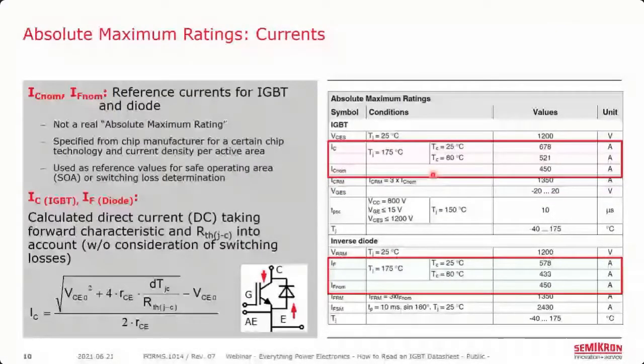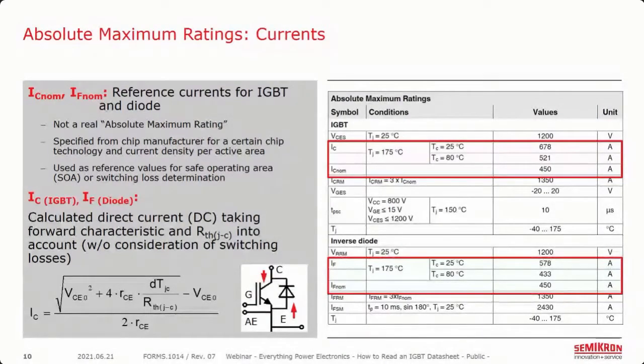The nominal current, ICNOM or IFNOM in the case of the diode, refers to the direct current rating of all the paralleled IGBT or diode chips that make up a single switch. This value is carried over from the chip-level data sheet. For example, in the case of this 450-amp module, three 150-amp ICNOM chips are paralleled to give us that 450-amp value.